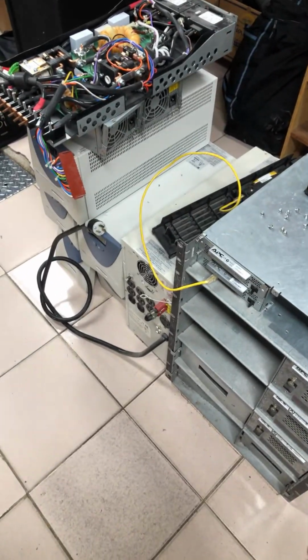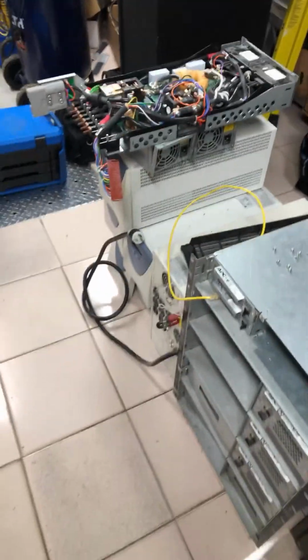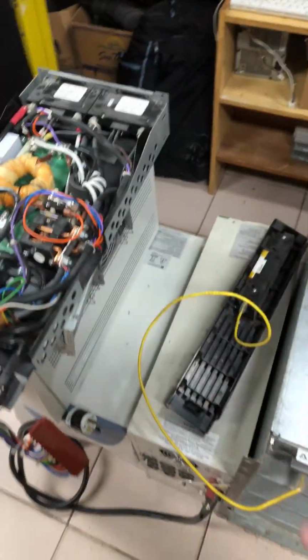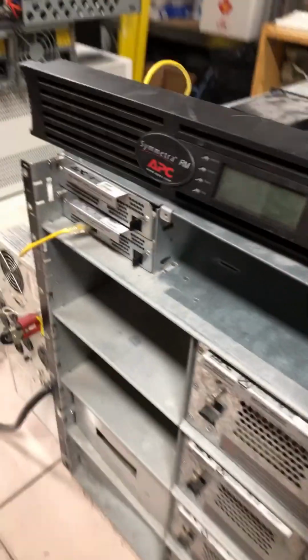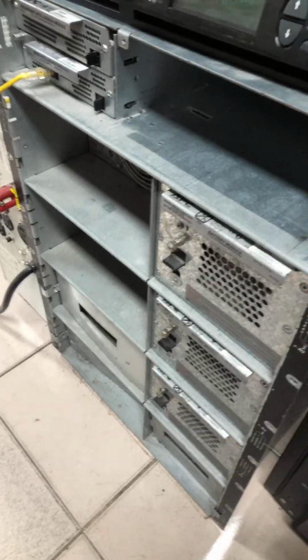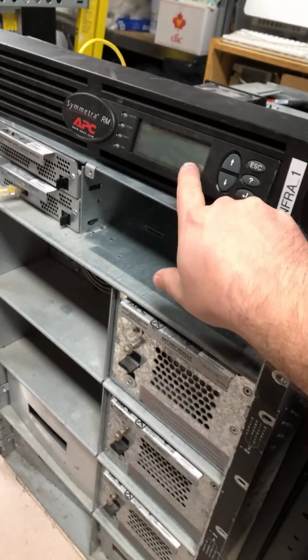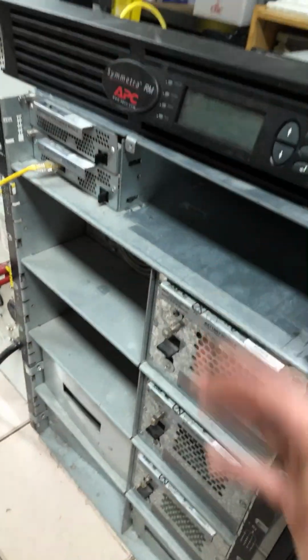For those just tuning in, the reason I'm pulling this out is because of the screen here, the main screen for the entire UPS system, a Symmetra. When you turn it on, it complains about a circuit breaker being open - specifically the input circuit breaker, which is this piece here. Even though it won't actually be tripped, it'll think that it is. That's basically what's happening.